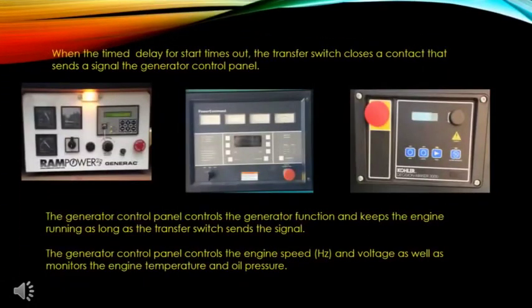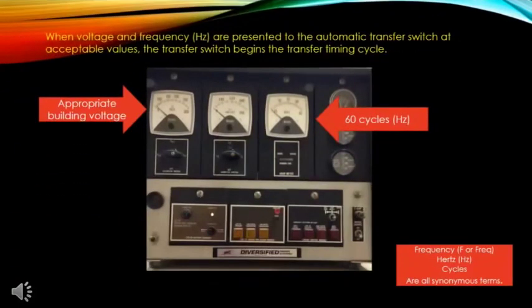The generator control panel controls the generator function and keeps the engine running as long as the transfer switch sends the signal. It controls engine speed and voltage, and monitors engine temperature and oil pressure. When voltage and frequency are presented to the automatic transfer switch at acceptable values, the transfer switch begins the transfer timing cycle. Your control panel should display the appropriate voltage and frequency.